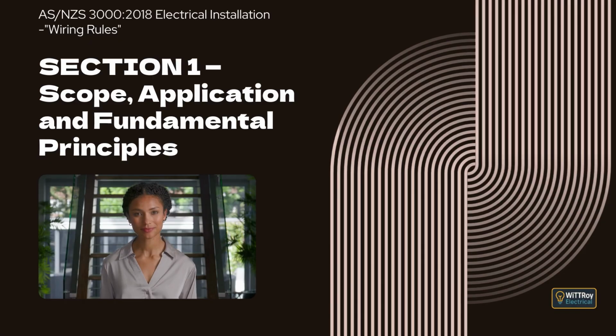Clause 1.4.68 is fuse. A fuse is a device that protects a circuit from excessive current by melting its fuse element and opening the circuit. A fuse includes all the parts that form the protective device. Clause 1.4.69 is informative. This means the content is for information and guidance only. It is not a mandatory requirement. Clause 1.4.70 is ingress protection classification, also called IP classification. This is the degree of protection provided by an enclosure, following AS 60529.